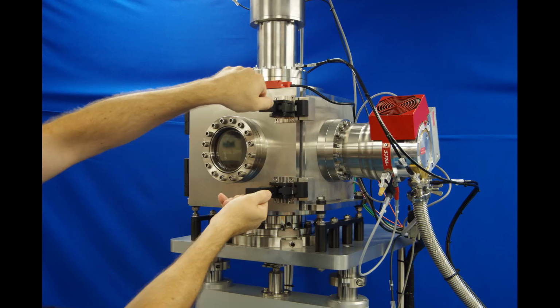Before closing the door, check that there is no debris on the O-ring. Close the door by pushing on the 2 handles to engage the locks. Note that from time to time the O-ring may need to be greased with vacuum rated grease to enhance sealing performance. After tests, specimens and assemblies are simply removed in reverse order.